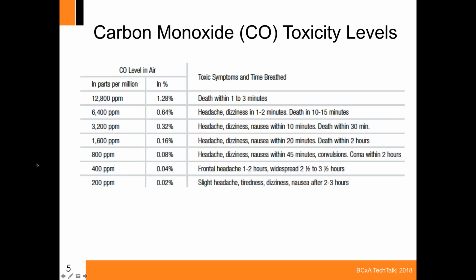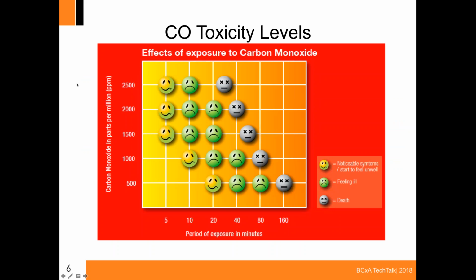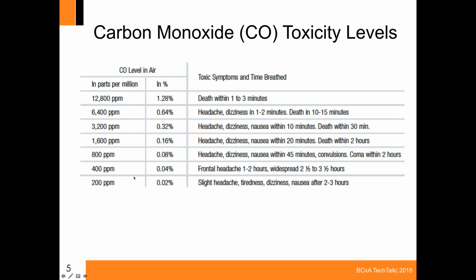So on to the toxicity levels. You can see that the lowest level shown on this table, on the bottom left-hand side, is 200 parts per million. And if you recall, that is actually what I said is our calibrated amount. We never expect the CO to get that high unless someone's maybe idling a vehicle right underneath one of the sensors. And it takes an awfully long duration even to start feeling any kind of health effects from 200 parts per million. You can see 2 to 3 hours. And then as we elevate up, the health effects get more and more. And this little pictograph shows how a person can feel from being exposed for durations at various levels. You can see on this, it's just at 500, which we would never expect in the garage. At 20 minutes, you're just starting to feel some noticeable symptoms.